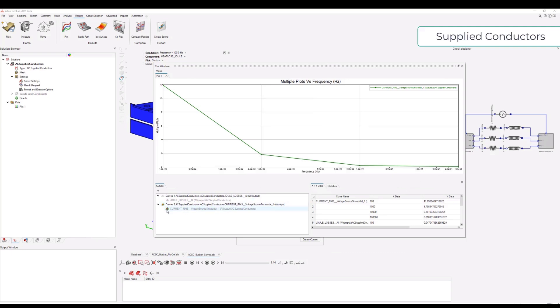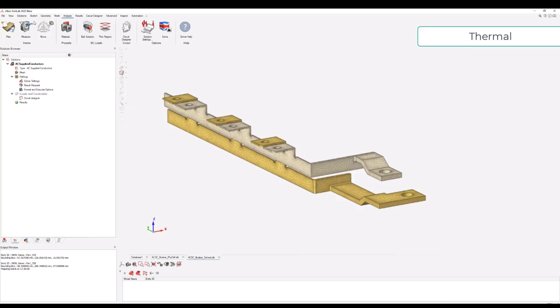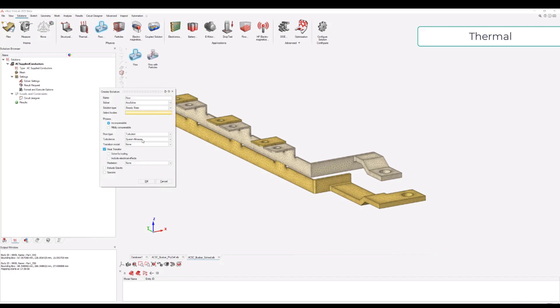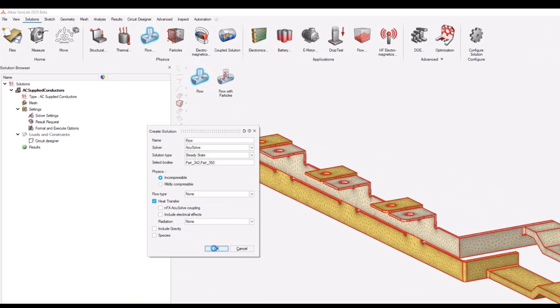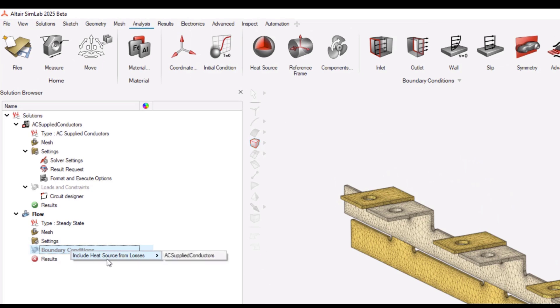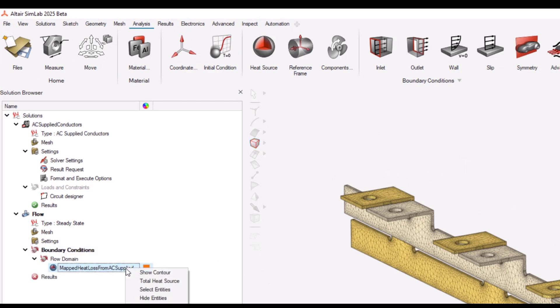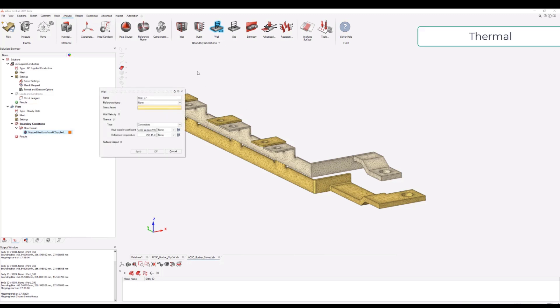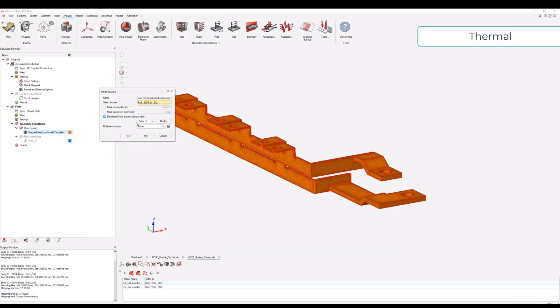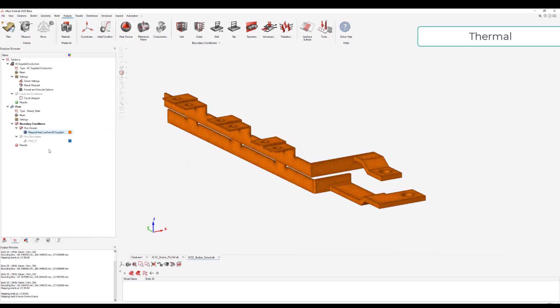That's all for the magnetic results. We can switch now to the thermal computation. For the thermal we can add a flow solution, which will call the AcuSolve solver. We can use that solver for CFD or in this case just a very quick thermal behavior with heat transfer on. The main part is to right-click and include the heat source, reusing it directly from the AC computation to this CFD computation. We can check the total heat source value - in this case it's very low because we didn't simulate a short circuit. We then define convection all around the busbars at 20 degrees as our boundary condition. This is a simplified thermal model, but we can do much more complex than that.